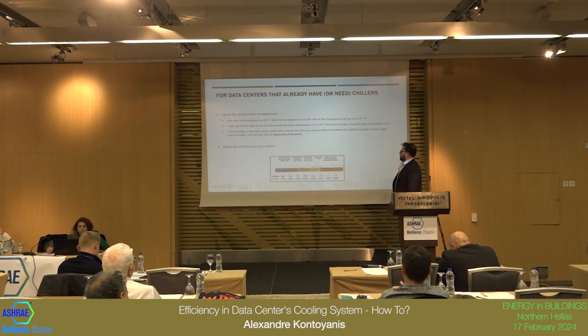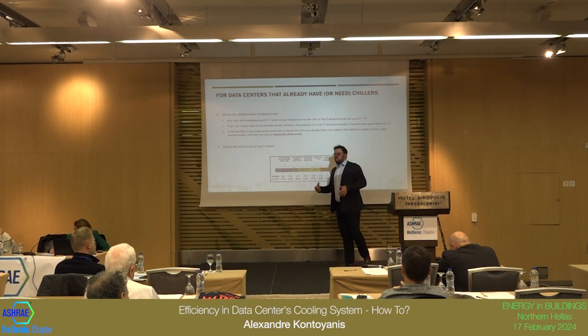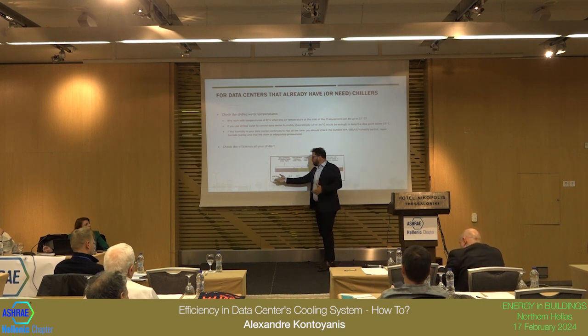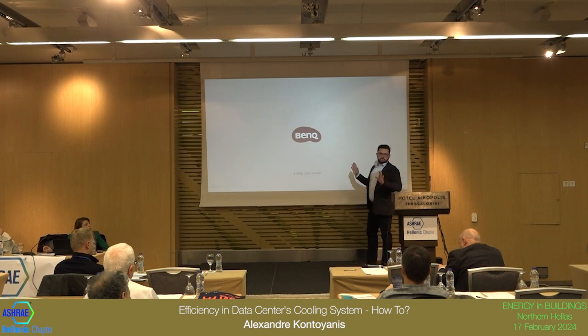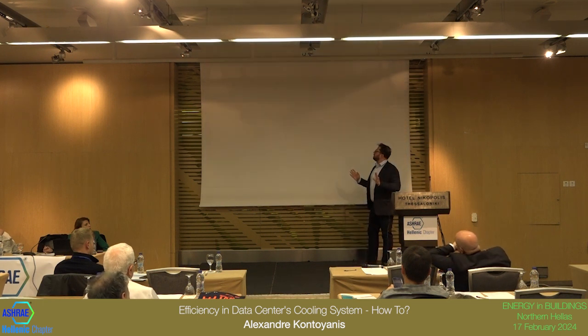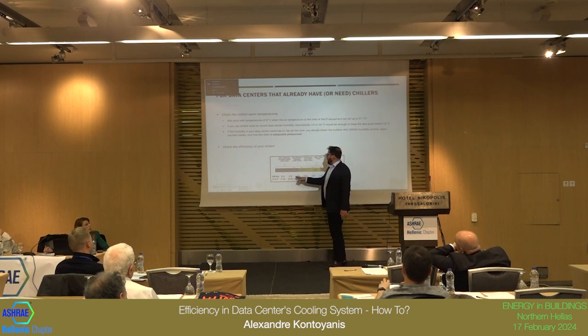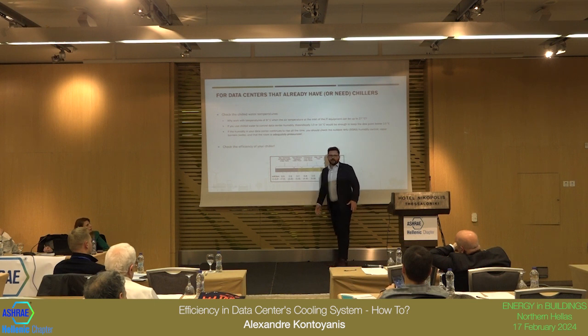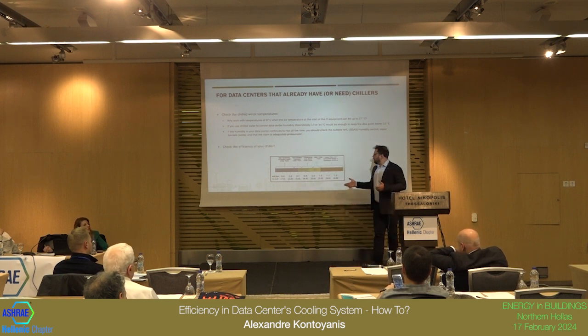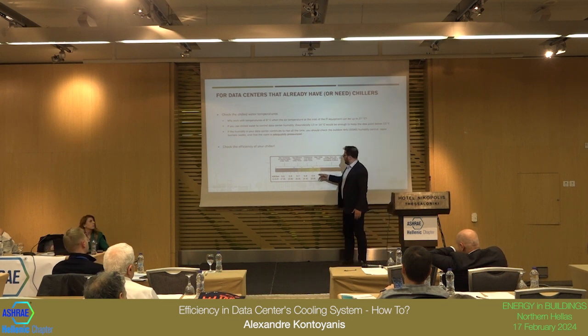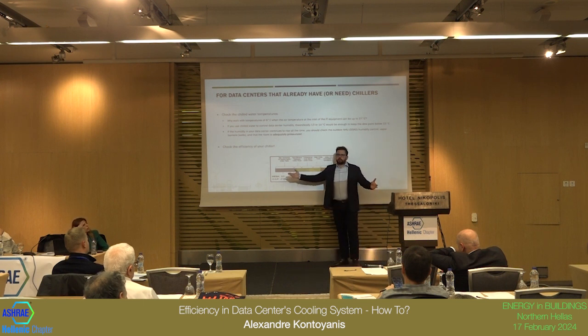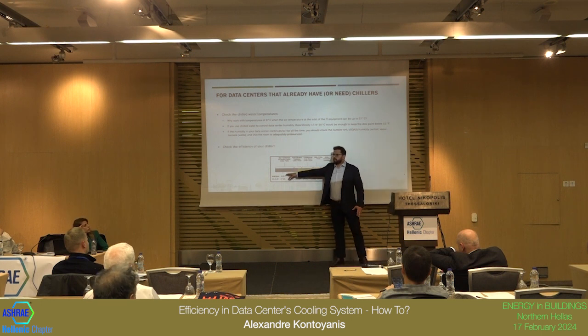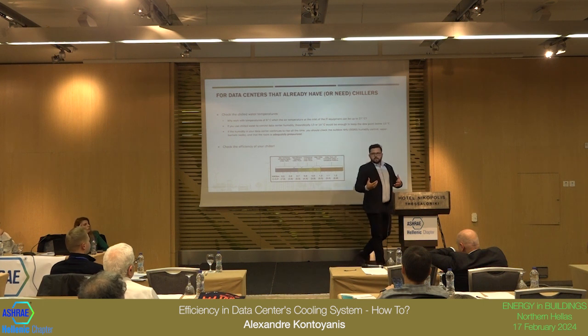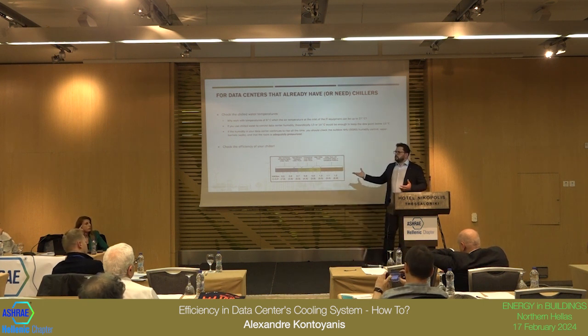Efficiency of your chiller. How is the COP of your chiller? There are other things to evaluate, for example IPLV, but let's check the COP. You have chillers right now with a COP of 7, very efficient COPs. But most data centers work with chillers of 3.9 to 4. I know it's fair, but you can go to the extent. So if you have to retrofit your chiller, look for this. It's expensive, yes it is, but the operation cost of the data center is much higher than the investment cost. It's much higher.